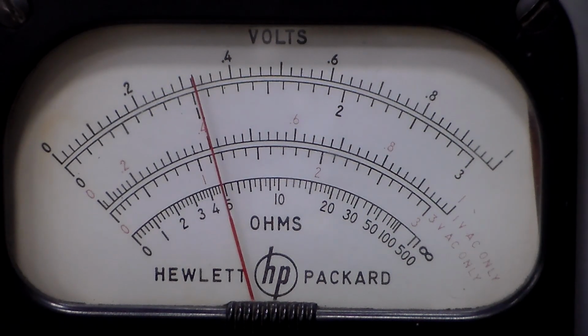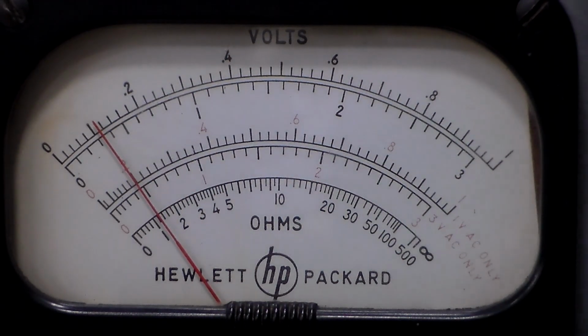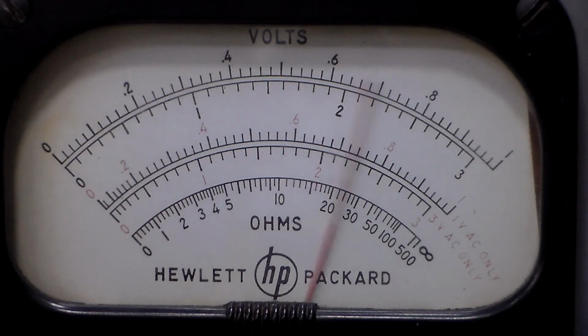So now if we go to, say, our 10 volt range, and it appears that down at 10% of the range we are about 1% in error, which that's 1% of full scale deflection, I might add, and Hewlett Packard give a specification of plus and minus 3% of full scale deflection, so it's quite a bit better than the absolute worst spec that they offer. So now if we go to 10 volts, and that's reading pretty well spot on. It's just a hair high, but that's okay. And then if we go to 30 volts range, we're reading just a little bit high. So generally it's reading slightly high, but that's fine.